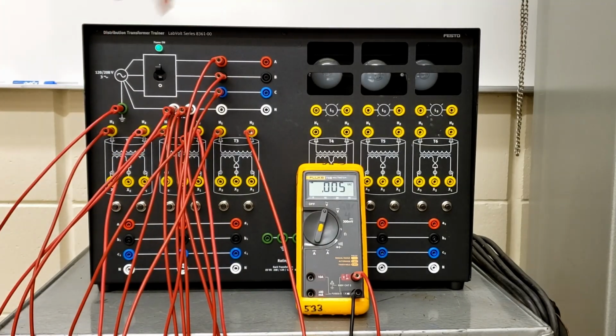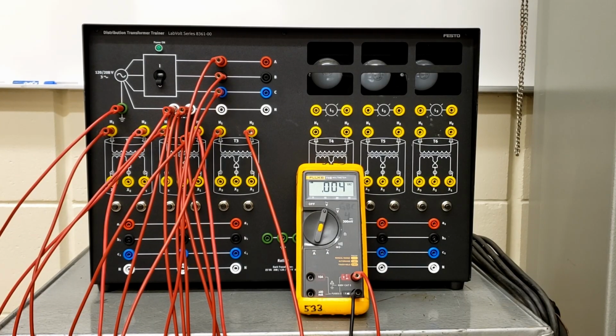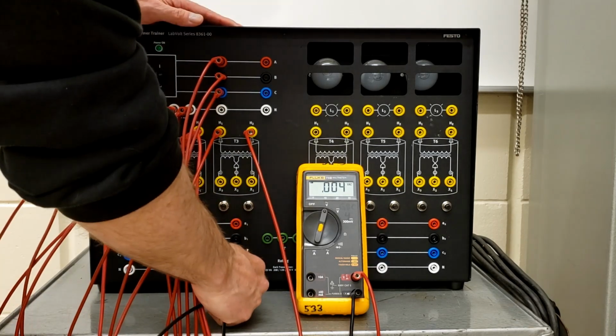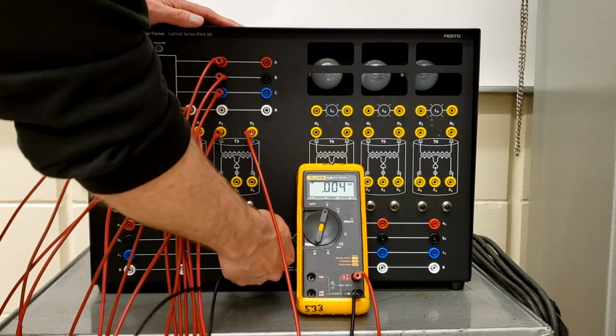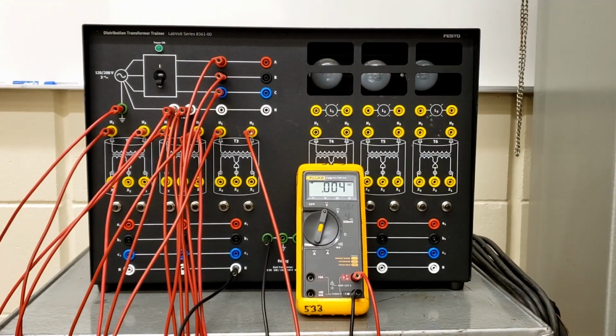Okay, primary is still good. On the secondary, we have a Y, so it looks like all our X2s are tied together, and that's going to the neutral, and the neutral is being grounded. So we'll ground the neutral first, then we'll tie all our X2s together.